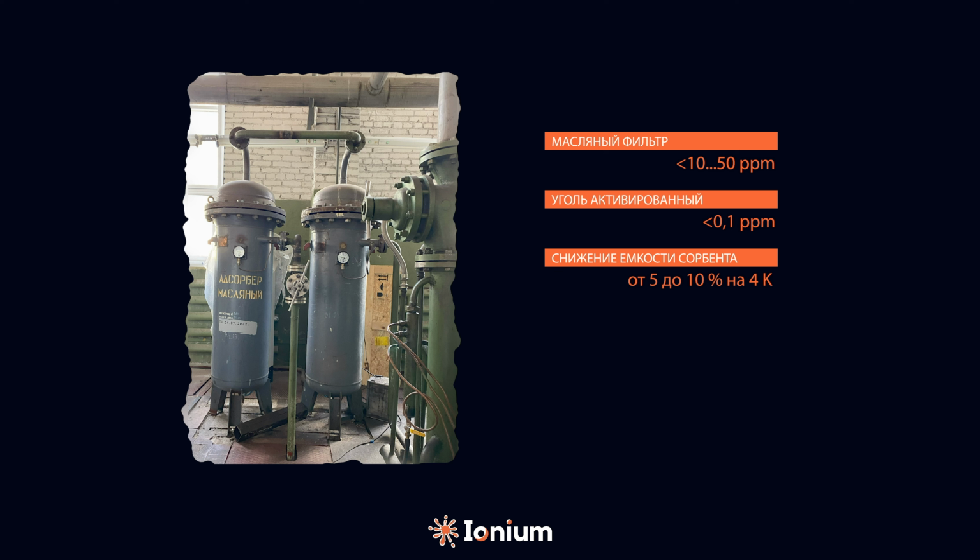In helium systems, it is not economically viable to regenerate them. The sorbent capacity then sets the operational lifespan of the adsorption module to at least the expected duration of a campaign at a facility that uses compressed helium. In certain scenarios, it's advisable to implement a system comprising parallel connected adsorption units with a manual control block in practice before embarking on a prolonged operation of a facility processing compressed helium. Only the first adsorber in the flow line is replaced. Typically, there's no oil bypass through the second adsorber.